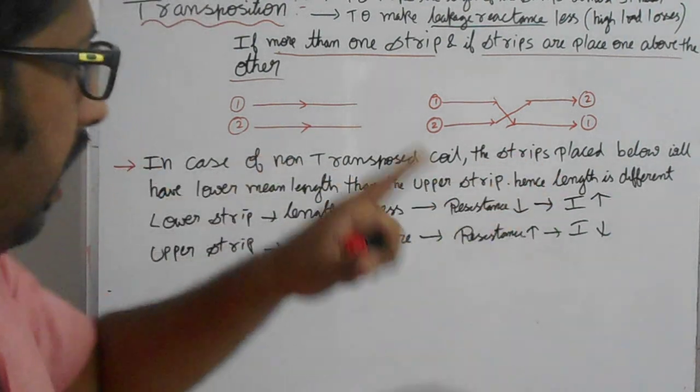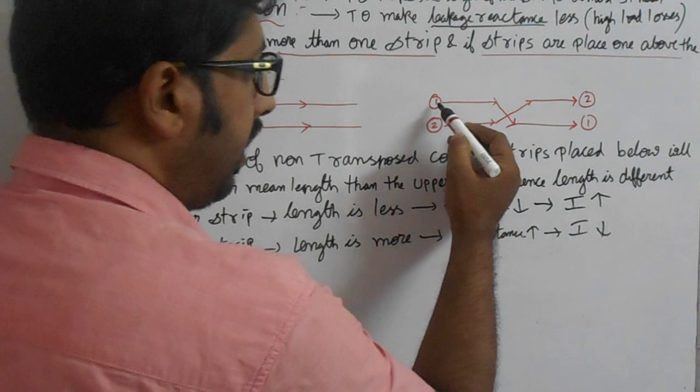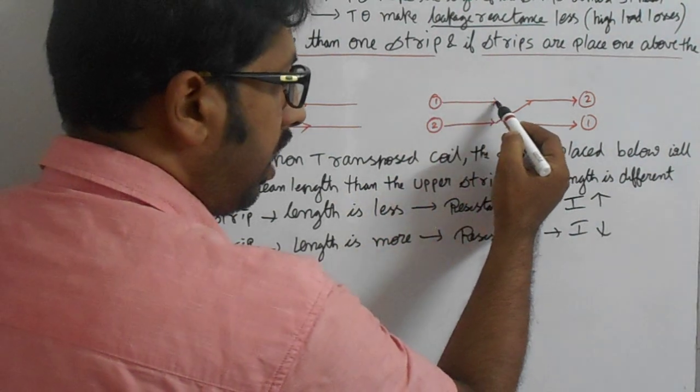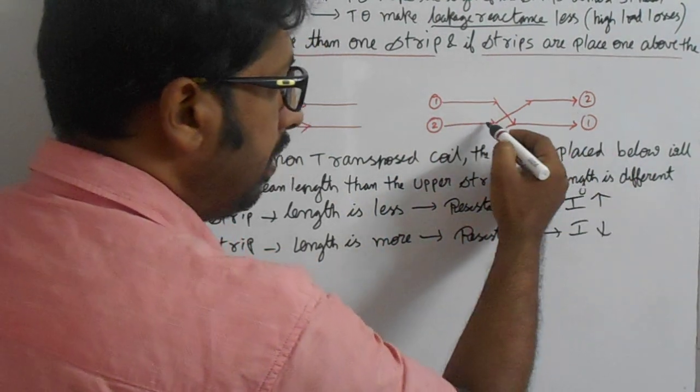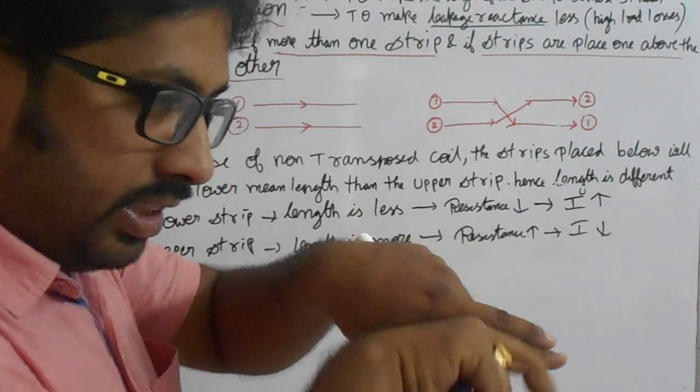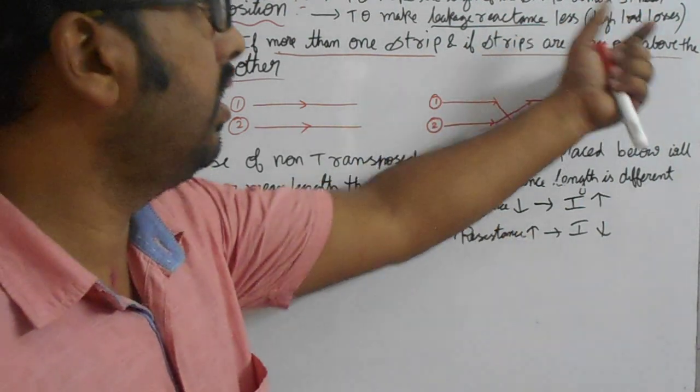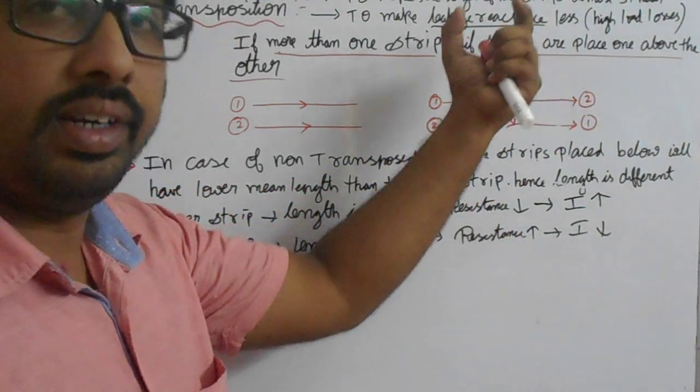If I wind right, this is non-transposed wire, this is transposition wire. As we turn, we are transposing such a way that we are making the mean length up and down and down, we are making the lengths equal so that the load losses and leakage reactance will be decreased.